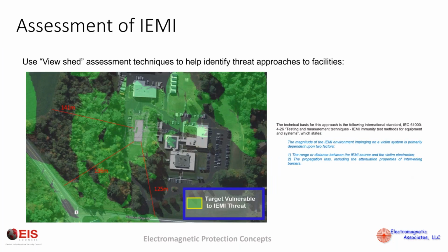One of the things that you can do with IEMI that you cannot do with HEMP is look at the lines of approach. And so you can use a view shed assessment technique to help you identify where you might be vulnerable to IEMI threats, and then you can take appropriate action to limit the IEMI threat in a particular facility. And to the right there's a technical basis for that, referencing an IEC standard that shows that you can take advantage of the distance away and anything that's in between a threat system and an IEMI threat. Next slide.